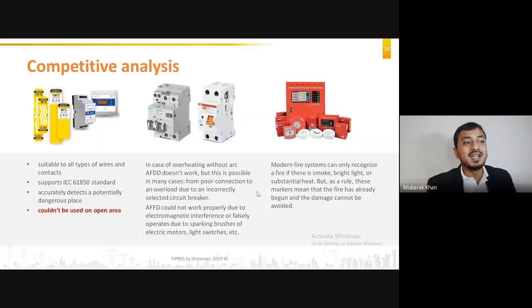so you will not be able to detect it. There is one more technology, an arc flash detection or interruption system, in which they are using optical sensors to detect the arc. In that also, as I explained, an arc may not always be there, but heat will always be there. So detecting the arc may help sometimes, but detecting heat will help most of the time. Moreover, these two devices don't compete with each other, they complement each other. You should have an arc flash detection system also, because it is a different kind of detection for a different scenario. It also prevents fire. FIPRES may detect the arc flashes, but not always. So these are two complementing products.